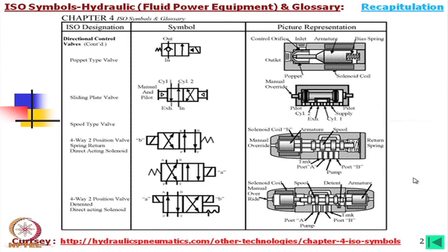First of all, we will recapitulate some symbols. This is a poppet-type check valve, but it is pilot operated so that we can make the line flow through. Normally oil is coming from one side and cannot go the other side, but we can move this poppet to allow flow in that direction. In this case, it is solenoid operated — if we move it, oil will flow through.